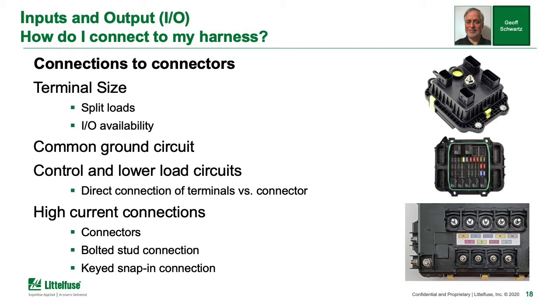Terminal size is very important. You need to think about what the load is you're carrying, how many amps that terminal can carry, and whether you need to split loads. In split load situations, you're taking a higher current circuit and splitting it over two smaller terminals. Do I have enough I/O to handle all the circuits I want, including my power and all my high power outputs?